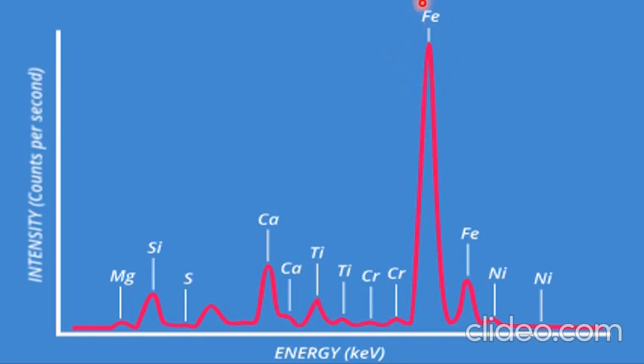Secondary X-rays generated in XRF spectroscopy may include K-alpha, K-beta, K-alpha 1, K-alpha 2, K-beta 1, K-beta 2, L-alpha, L-beta, and others. On the basis of these emitted X-rays, the energy peaks may vary.